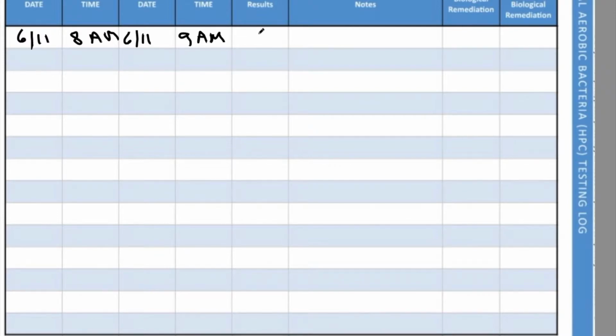If you get 10,000 or less, you're in pretty good shape in terms of bacterial levels in cooling towers. Remember, this is not drinking water we're dealing with. So if you have less than 10,000, that would probably usually be pretty routine. You can just write in here 'less than 10,000' - that symbol represents less than 10,000. That's the same thing as the 4 zeros you have there. So you can write it in as 10,000, or you can write it as 10 to the 4th.